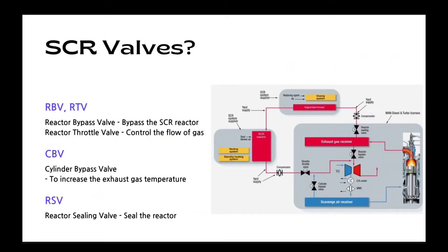What is the role of SCR valves? RBV and RTV. RBV is the reactor bypass valve. It is used to bypass the SCR reactor during Tier 2. When changing mode from Tier 2 to Tier 3, RBV will be closed gradually after RTV is fully opened. And RTV is the reactor throttle valve. The flow of gas is controlled by this valve during heat up.